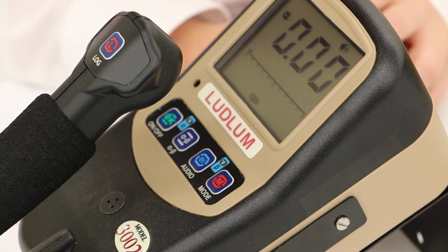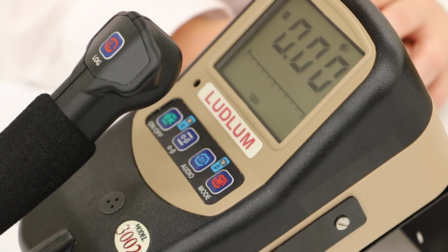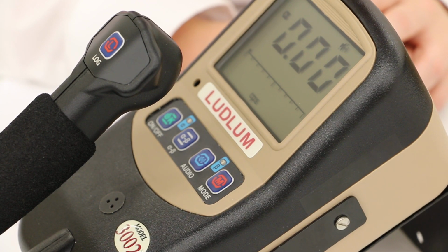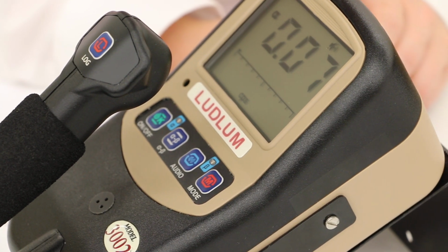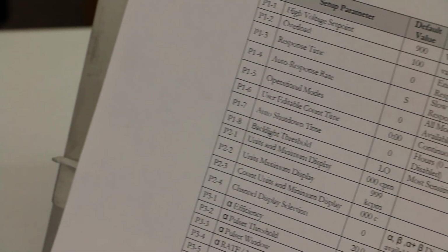If you get into the device menu and there is nothing blinking, odds are your instrument has protect mode enabled, and to disable that you would have to remove the can and rotate the dip switch. Inside our user's manual, you will find a list of all the parameters in order, which page and which selection in that page that they are.